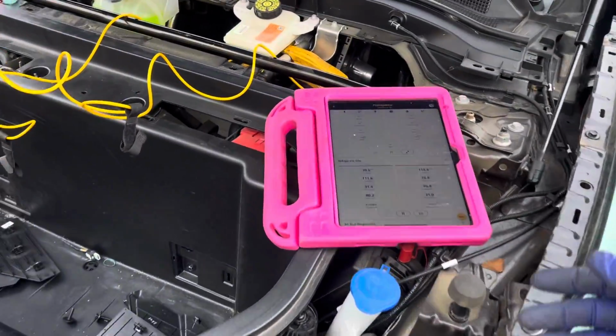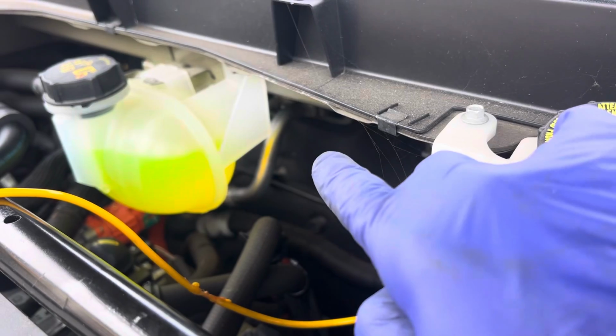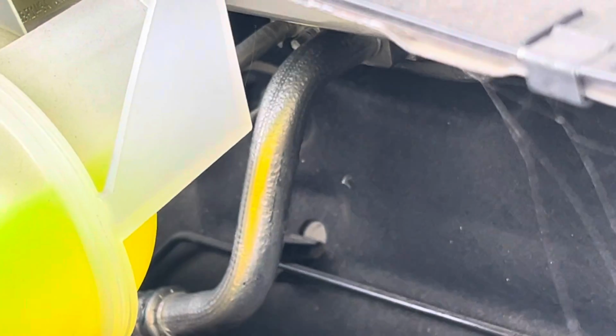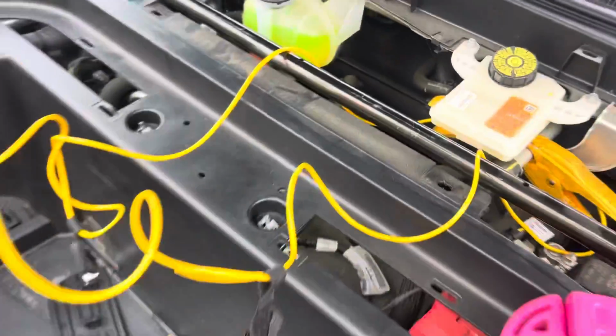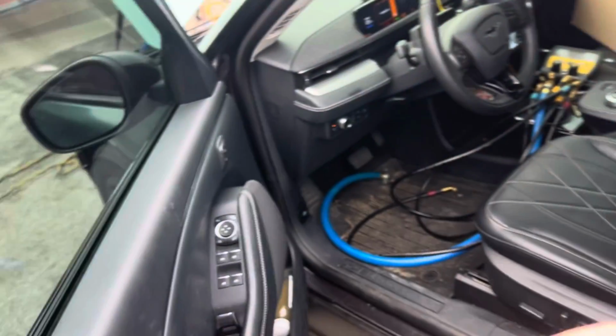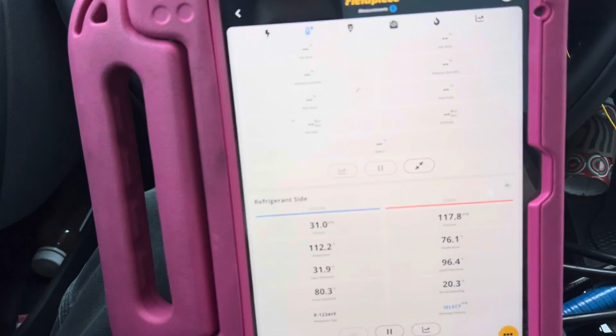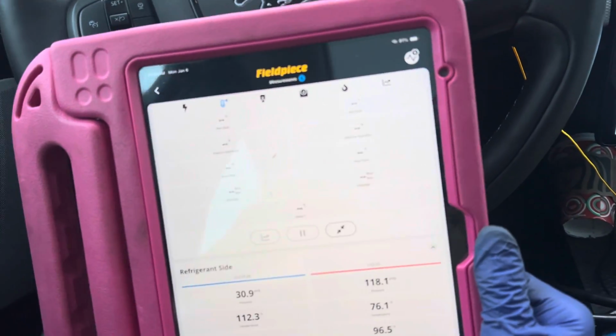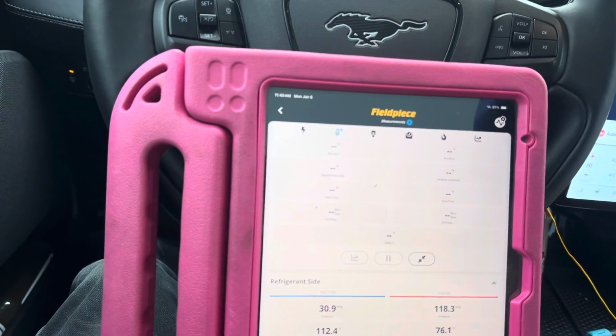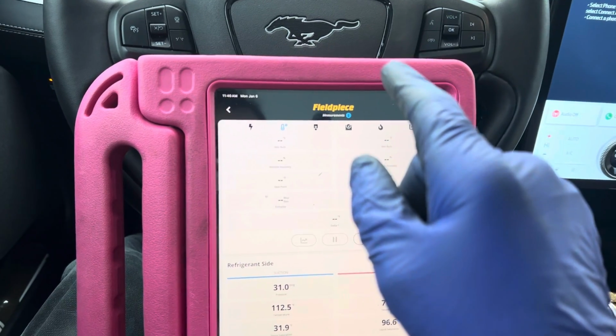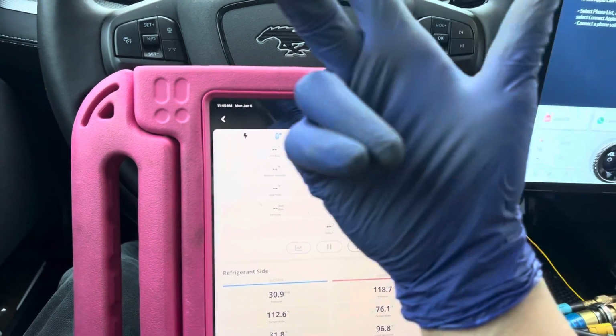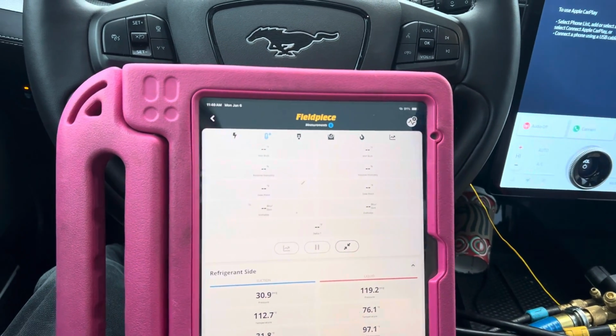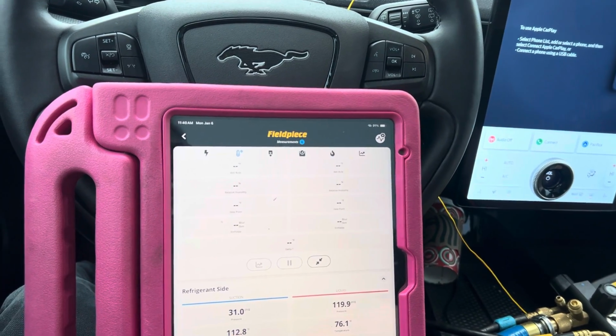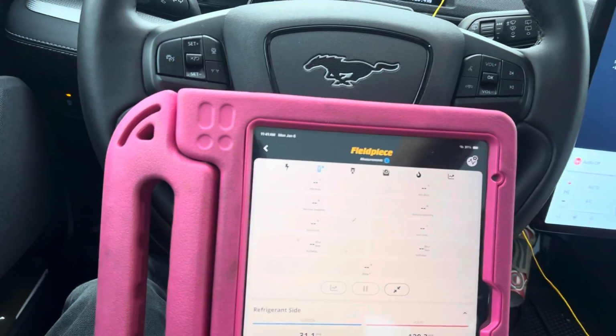So of course defrost always wants the AC on, and you could actually see all the water developing. Let's see if I could zoom in there. Right there, that big metal line with all the water drops on it, because we're a little foggy out. There's a little humidity in the air. Let's go play around up here. So this one is not doing reverse refrigerant flow like some of them do. This one is relying on just flowing the hot discharge gas of the compressor into a plate heat exchanger. So some flow the hot discharge gas into the plate heat exchanger, and other ones will reverse the flow of the gas of the compressor and actually make the evaporator a heater and the condenser basically the evaporator. It'll get cool outside.